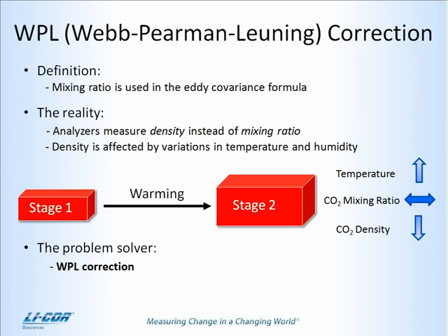What are your thoughts? Yeah, I can take this one too, Jihong. It's a good question, and I believe there's not a real clear answer here, but there's certainly things to think about. You want to have enough separation to avoid disturbance, so each sensor is not affecting the measurement of the other one.